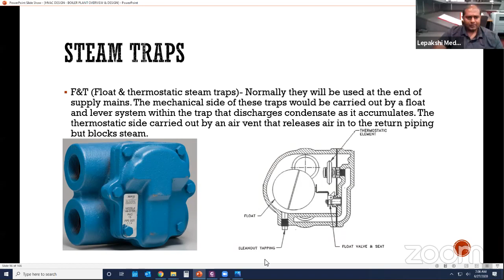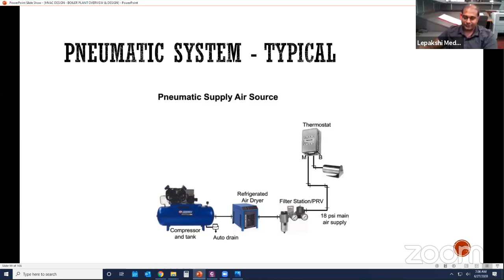And the pneumatic system. What is a pneumatic system? You'll have an air compressor over there, and that is tied into this. You'll have these copper lines running throughout the building, right? So you'll have a thermostat over there. This main line is going to the thermostat. Whenever the air pressure is set over there, it's going to open up something and let the air pass through into the control valve, and the control valve will open and the steam will pass through. Pretty much, you'll set the thermostat to whatever temperature you want. Whenever the temperature falls below that particular temperature, it's going to let that air go through and tell the control valve to open up to let the steam pass through. That's what it does. It's pneumatic.